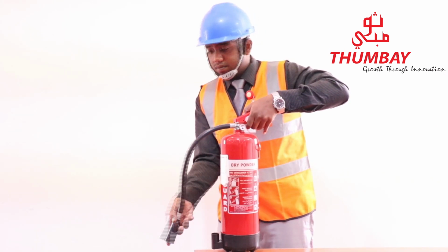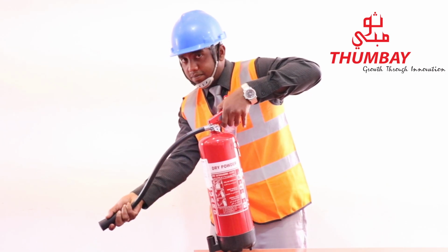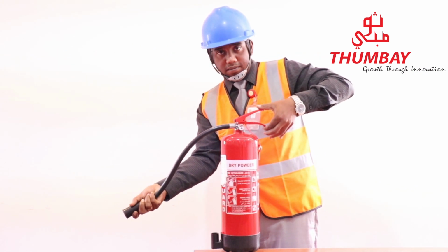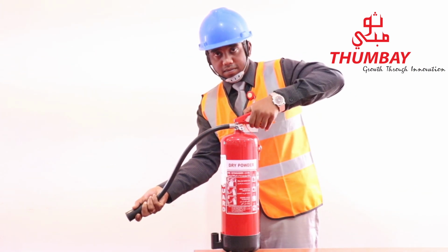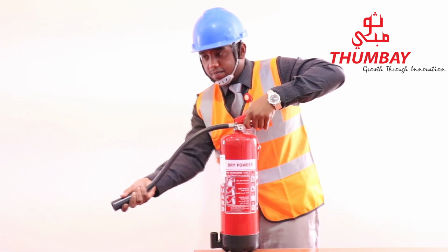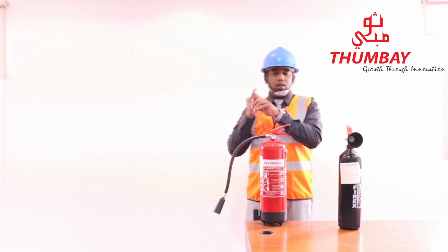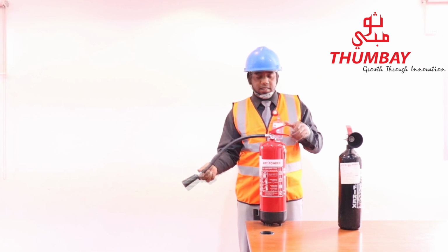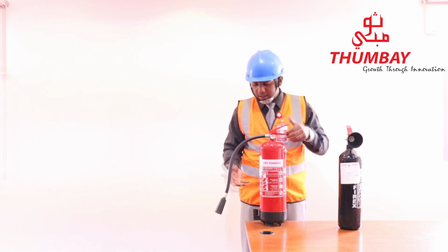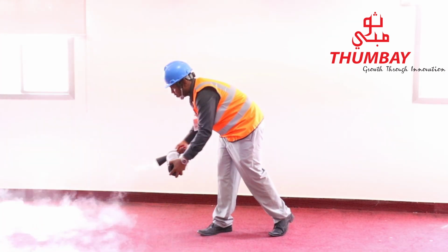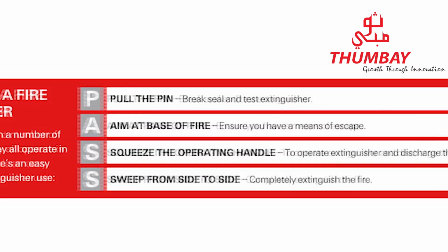Aim at the base and squeeze the lever to deliver the agent, which is highly pressurized, and sweep side to side until the fire is completely put off. So this is the way: pull the pin, aim at the base, squeeze the lever, and sweep side to side. This is the PASS method.